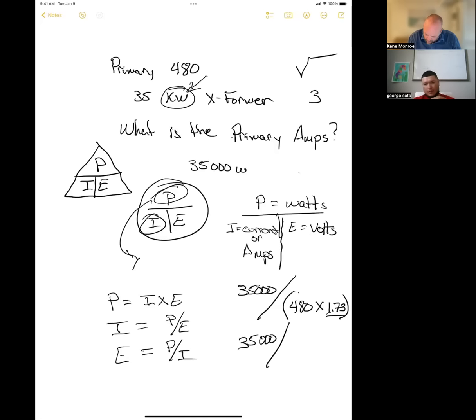And that equals 830.4, because we took this and multiplied it. Okay. And now by code we can drop the 4, and then we just divide. So you take this 35,000 and divide it by 830, and you come up with 42.1 amps.